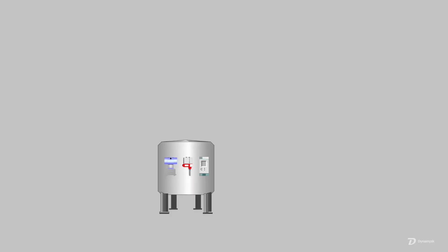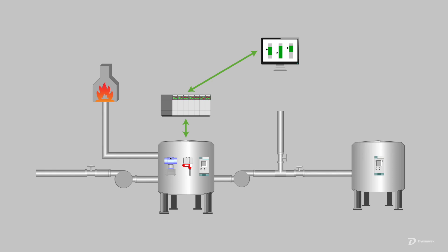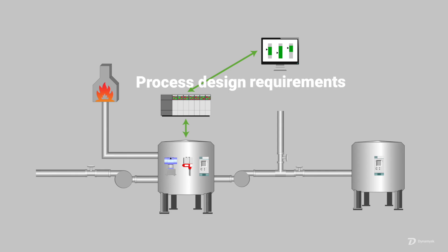When building any complicated systems we first compartmentalize, try to simplify, then build the complexity. So let's talk about simple loops. For basic process information displays like temperature and pressure, we may have an analog signal to the control system and display it on the HMI. For a simple control loop we may have an analog input, a control algorithm, and a simple analog output. There may be interlocks for mechanical protection — stopping a pump if a level in a vessel is too low, or a temperature interlock stopping a furnace from heating up so much that it damages the internal tubing. These simple loops are controlled within process specifications laid out for product quality requirements, process design requirements, and safety requirements.